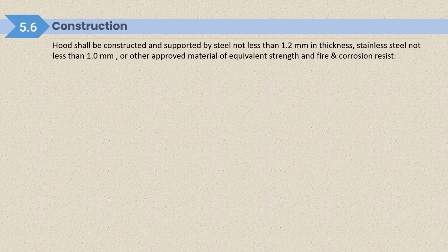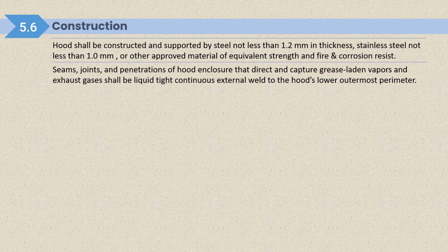Constructions. Here it talks about the construction of the hood and the duct. Hood shall be constructed and supported by steel not less than 1.2 mm in thickness. Stainless steel, if it is stainless steel, in that case not less than 1 mm, or other approved material of equivalent strength and fire and corrosion resistance. Seams, joints and penetrations of the hood enclosure that direct and capture grease laden vapors and exhaust gases shall be liquid tight so that grease cannot leak from those seams, joints and penetrations.